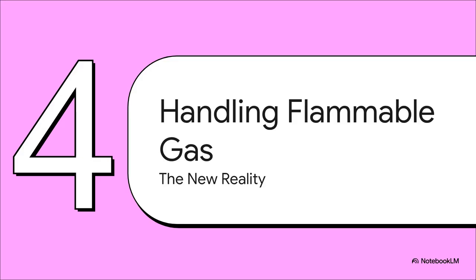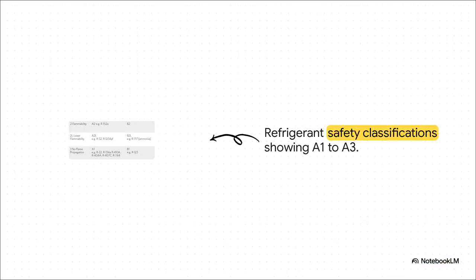Section 4. Handling flammable refrigerant gases. Welcome to the new reality. There is a massive shift happening right now. As we look at the safety classifications, you can see we are rapidly moving away from the safe, non-flammable A1 group, so gases like R22 and R410A. Instead, we're shifting up to the lower flammability A2Ls like R32. And in some applications, we're even seeing highly flammable A3 hydrocarbons like R290. Full safety checks are required across the board, but these new classes demand ultimate respect.